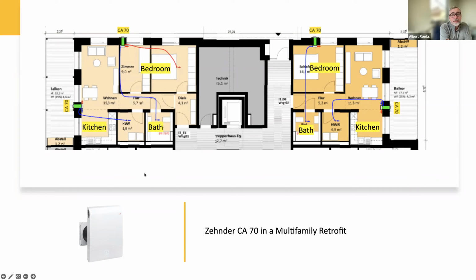And that's actually where the fans are. The rest of that white cover is all heat recovery or enthalpy recovery core, because you need a really big core to get that 85% recovery. And then the little white piece on the outside is just a little hood. So we put that through that wall in the upper left-hand corner, and there's a little tiny red arrow right at that unit, and that's giving fresh air to that bedroom.